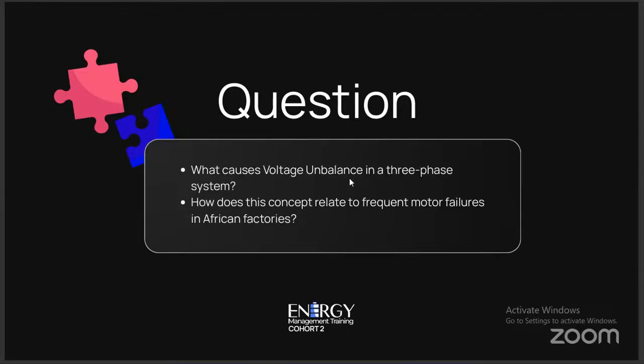Yeah, so causes of unbalanced voltage in a three-phase system. Basically, it's always faults in the distribution network. Sometimes a jumper may be weak or may even cut, and then you notice that phase will not be carrying the expected voltage. If you measure the voltage, it will be very low. Sometimes it is due to weak conductors, maybe hot conductors. This affects the voltage and could cause one phase to experience low voltage while the others experience normal voltage. All right, thank you very much.